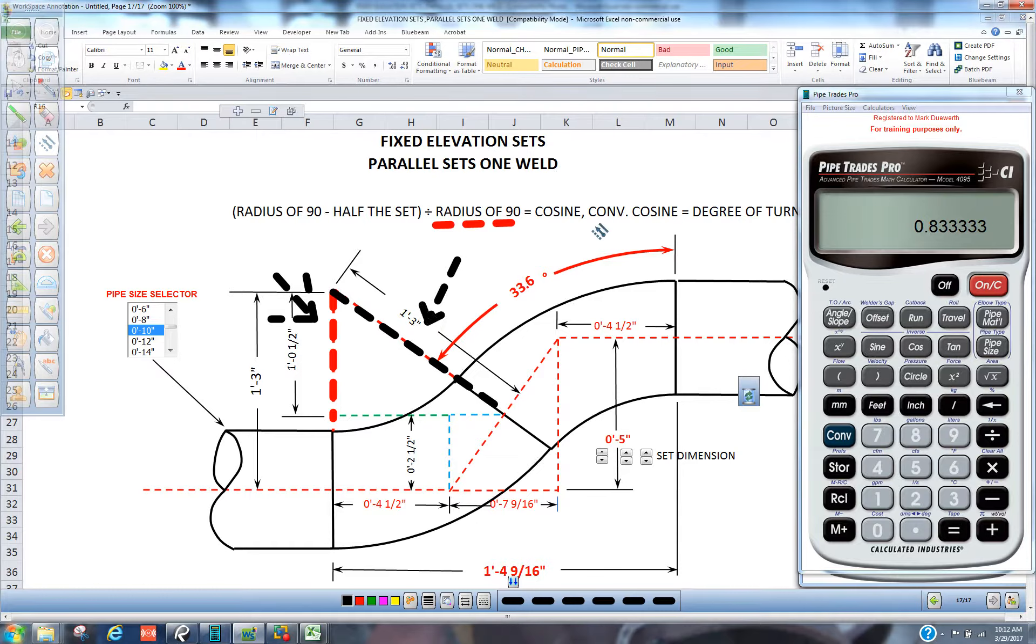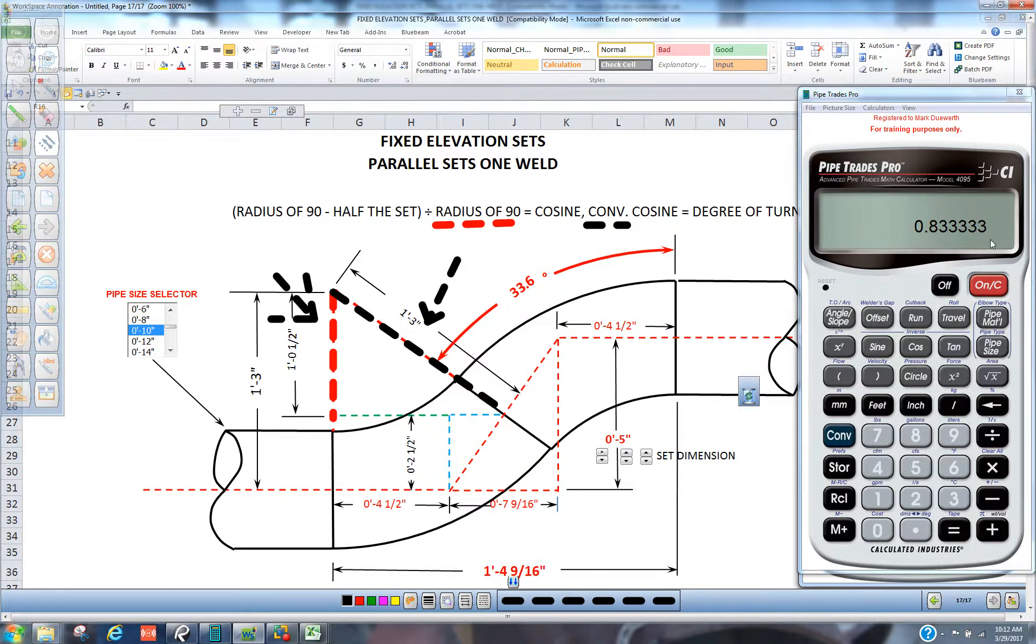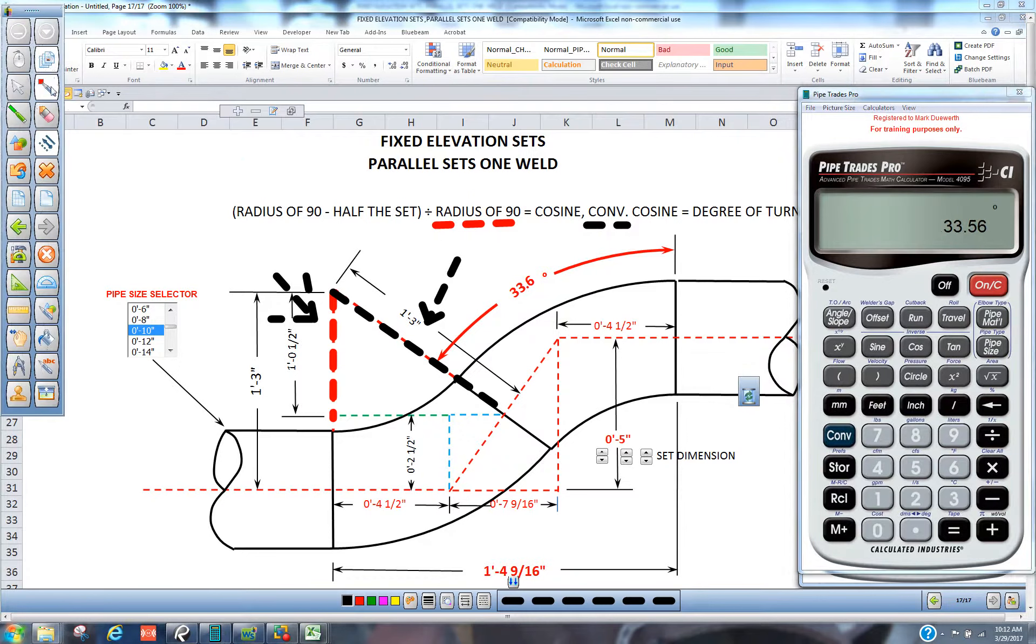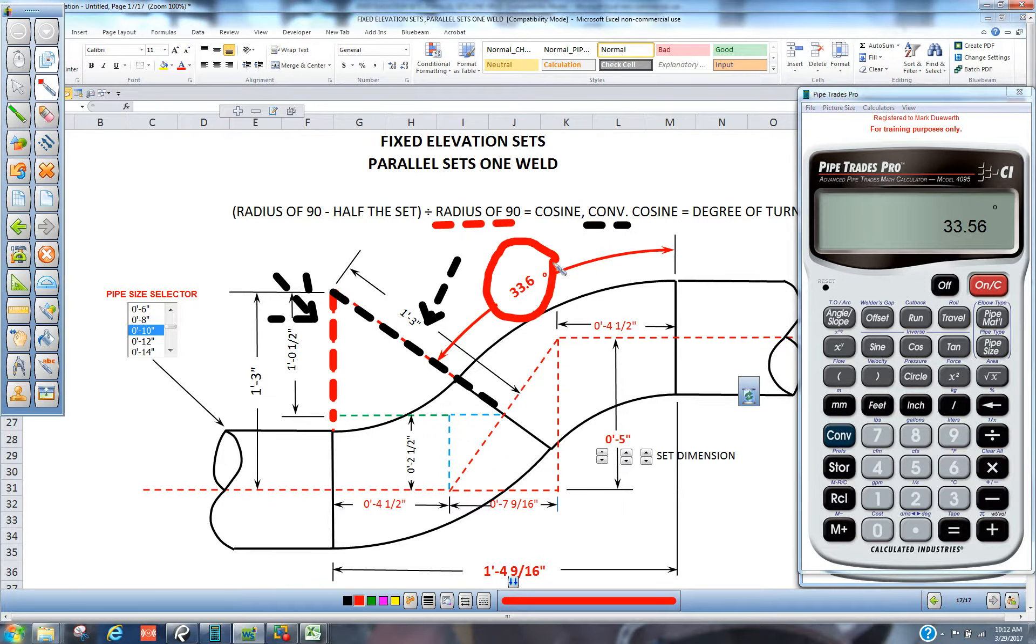Now when we press convert on the calculator, convert cosine, that will take that trig number and turn it into the degree of turn. Press convert cosine. Your angle of your fitting is 33.6 if you round up.